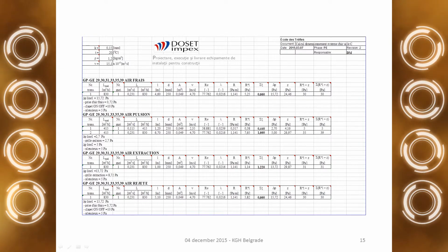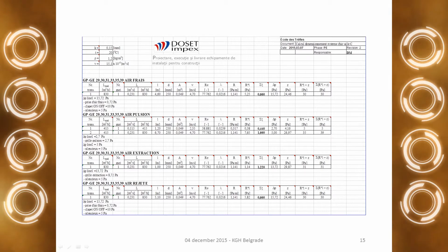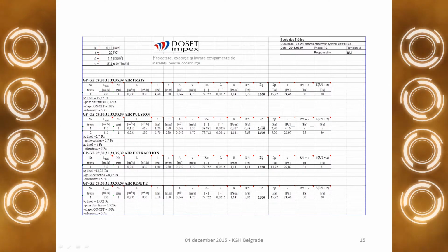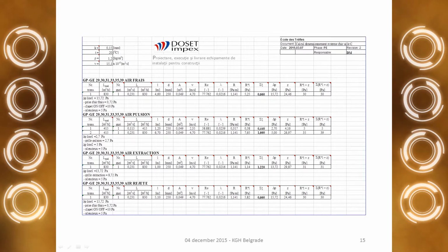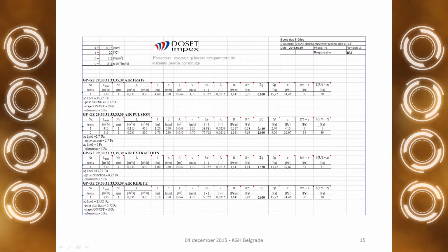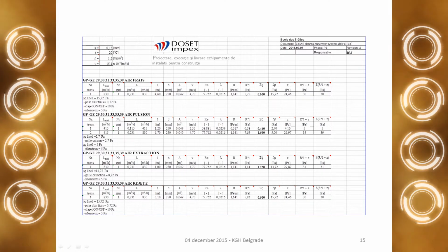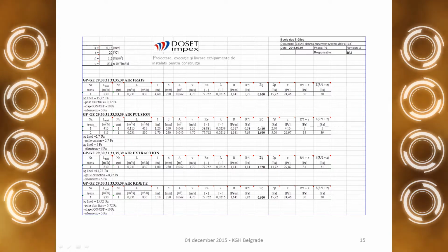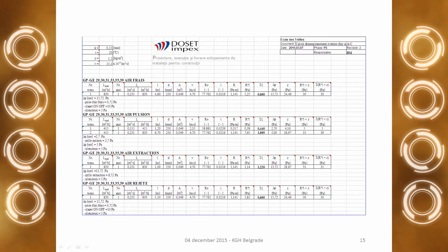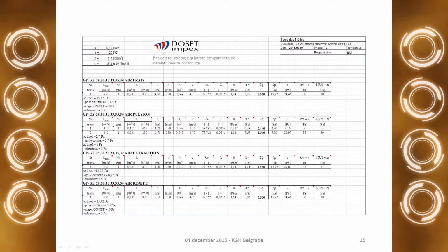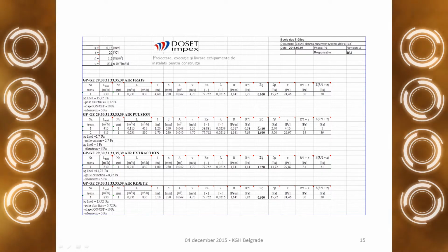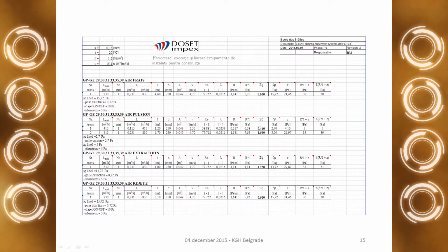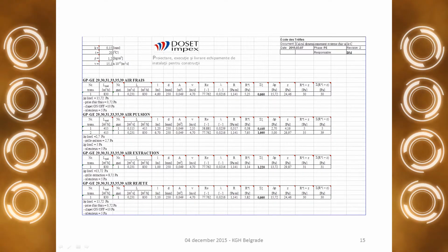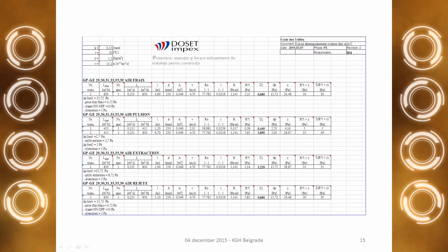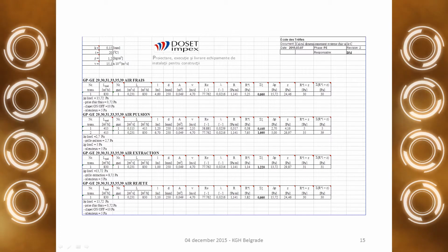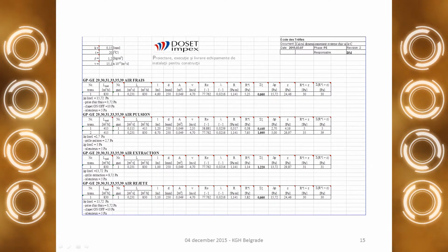In that way, we choose the air handling units, which is a Swegon, an air handling unit for each classroom, with a high efficiency for the heat exchanger at 90%. Taking into consideration the nominal condition at -8 degrees outside temperature, 20 degrees inside temperature. Also, the efficiency was related in accordance with the standard EN 308. And also taking into account the engine of the fan.